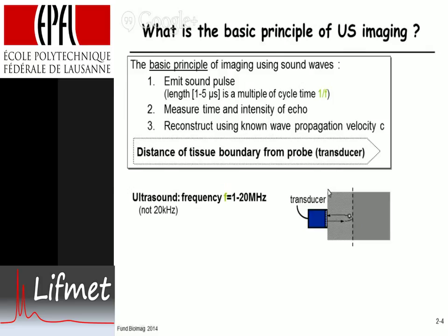The sound wave is emitted and comes back, and from the time and intensity of the echo one can calculate the distance of the boundary from the probe. The distance is very simply: speed times time divided by two. The time is from when the pulse was emitted until the echo is received. The factor of two accounts for the sound wave having to travel into the tissue and back — it travels twice the distance.